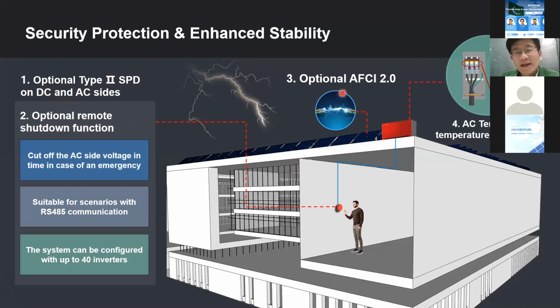We have a leading technology called AFCI, detecting arcs in the PV modules and PV arrays. Frankly, our AFCI has already been upgraded to the second generation compared to AFCI 1.0. The second generation can successfully monitor and report over 90% of arcs that happen in your PV panels. GoodWe's products are the only string inverters that integrate AC terminal temperature detection, giving more safety protection for utility power plants or C&I projects.